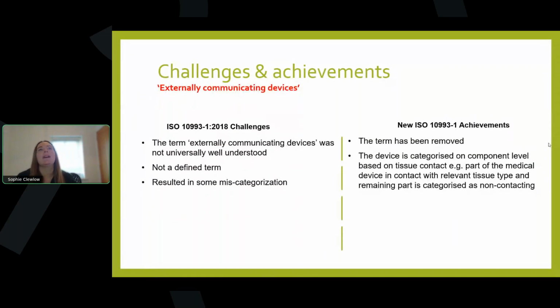Thank you. Another change is with regards to terminology. So you'll have probably noted, if you've had a chance to review, the term externally communicating has been removed from the tables. This term wasn't defined in the previous version of the standard, and what was meant by this wasn't completely clear, so it has led in the past to some miscategorization. And so to tackle this, the term has just been removed from the document, and the focus has now been put on the type of tissue contact for each component rather than just that category of device. And next slide, please, Michelle.